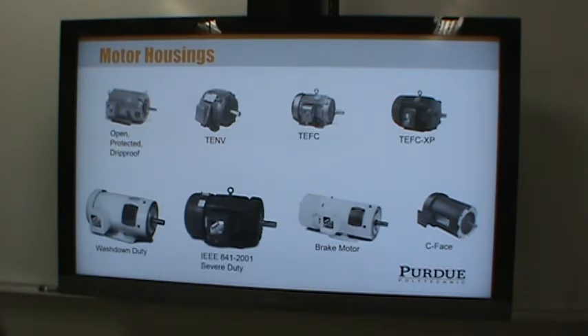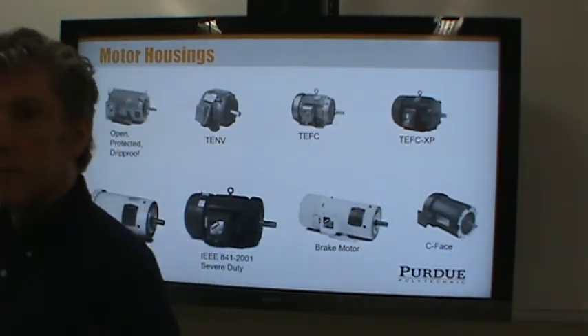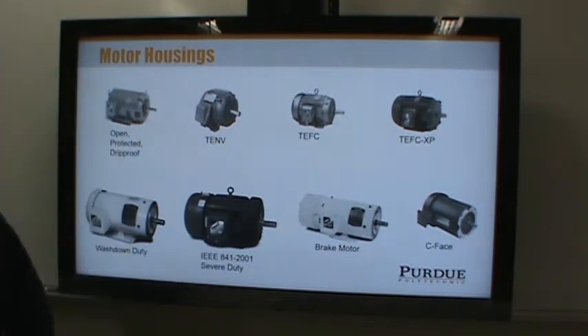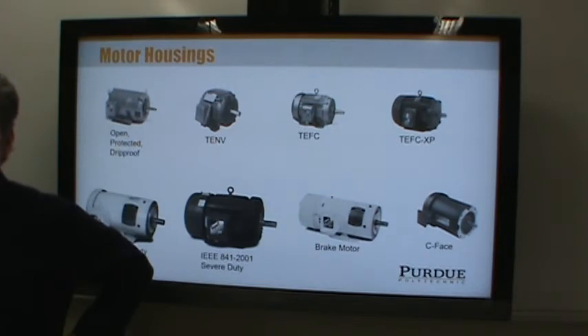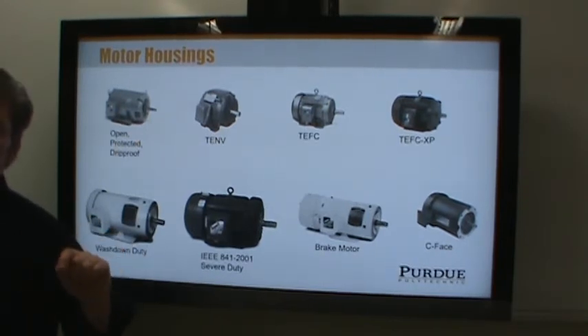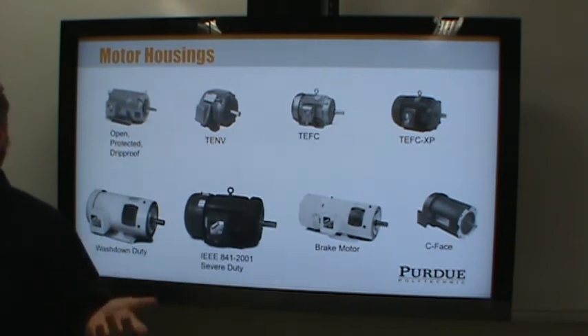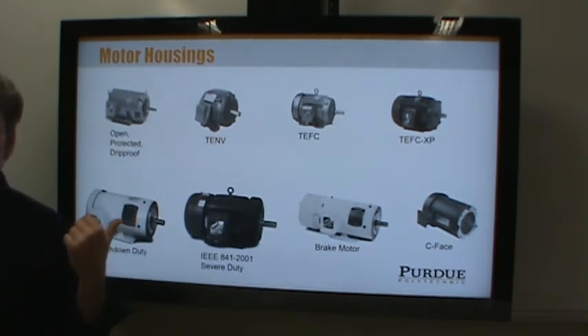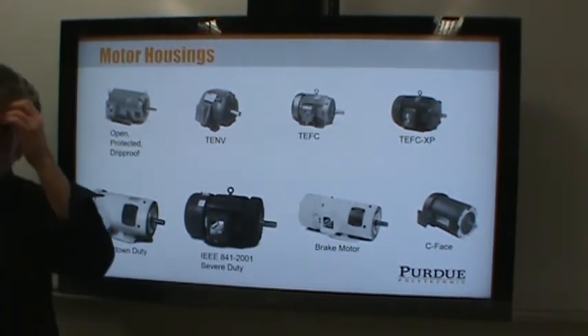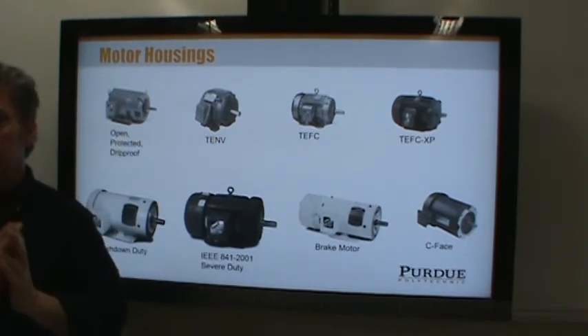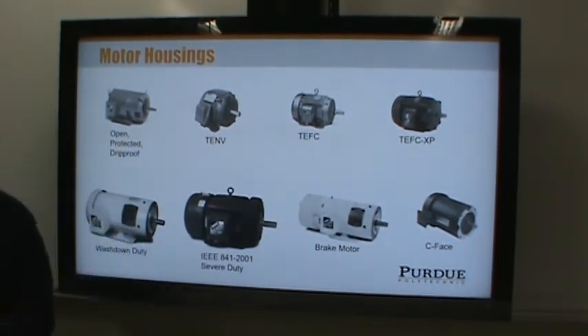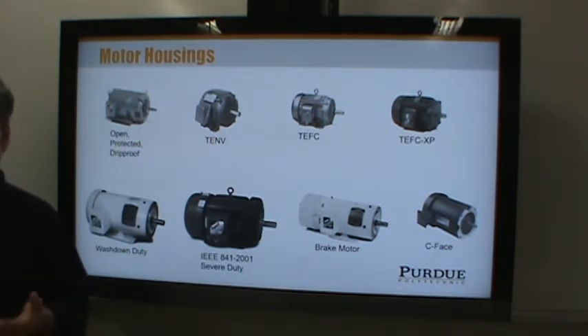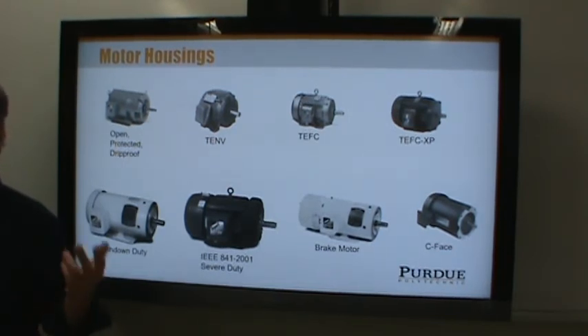A student mentioned that many brake motors they've used are electromagnetically activated, and that there are scenarios where applying current engages the brake and scenarios where disconnecting current engages the brake. This gets into the safety question of whether you want the motor to coast down or stop immediately when power fails. There are many brake types available — friction brakes and eddy current brakes are just two options.